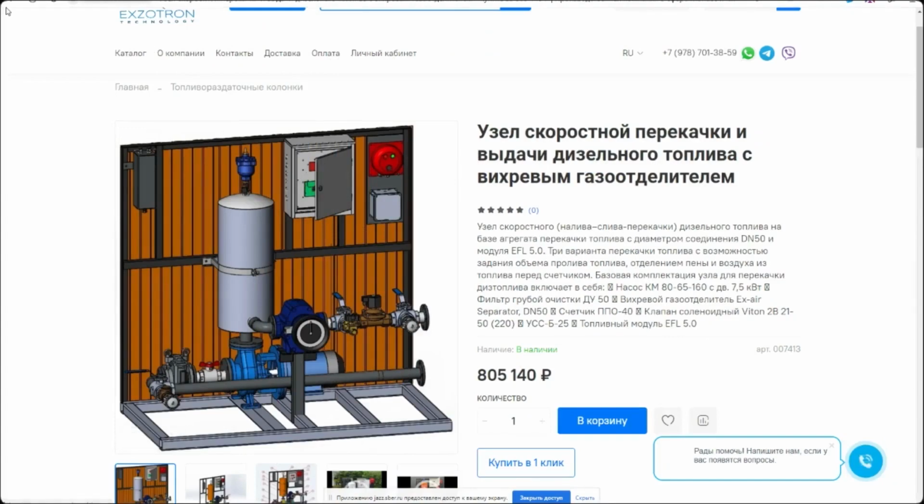Here we see 2 pipes, so that it is possible to pump out into the tanks, and pump from them. If needed, it's even possible to pump between tanks for neutralization with counting. The gas separator is crucial as it eliminates foam and air, making it an essential component in the process. Therefore, any chance of winding the counter is ruled out, ensuring consistently accurate and reliable readings at all times.